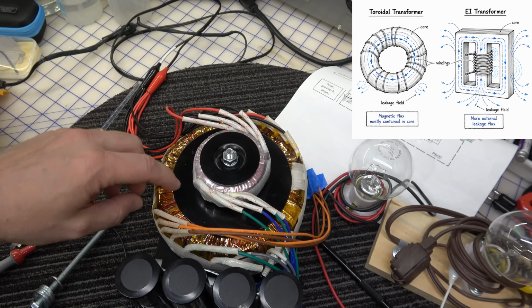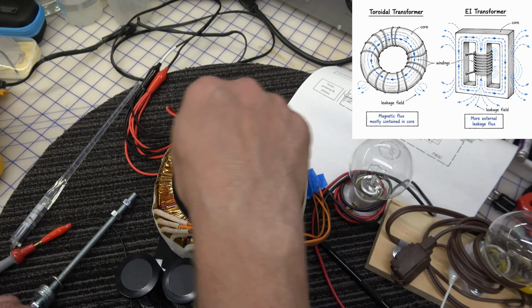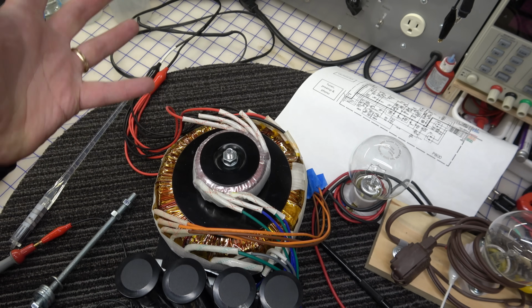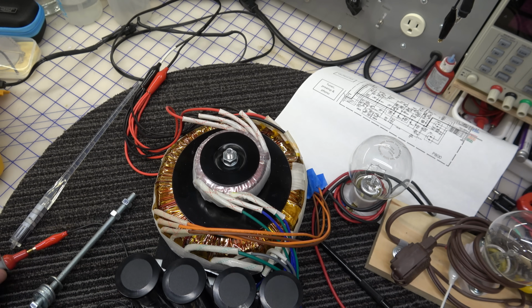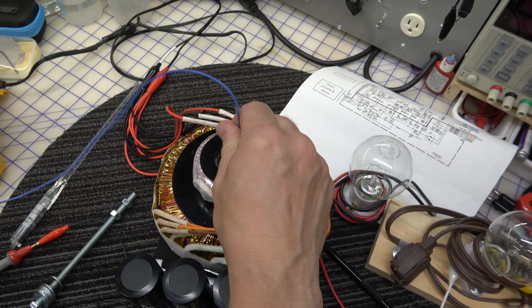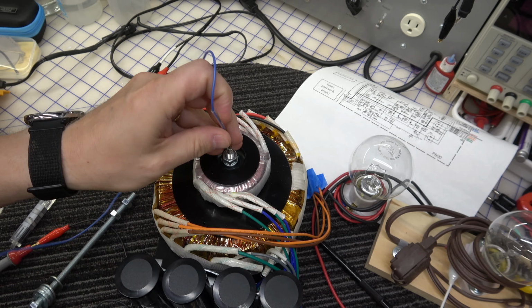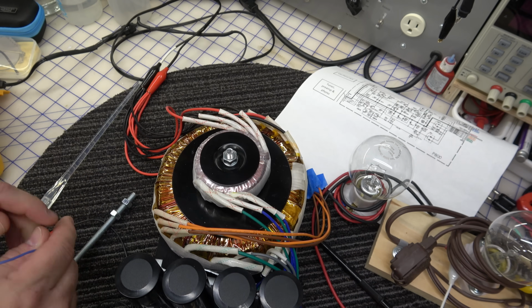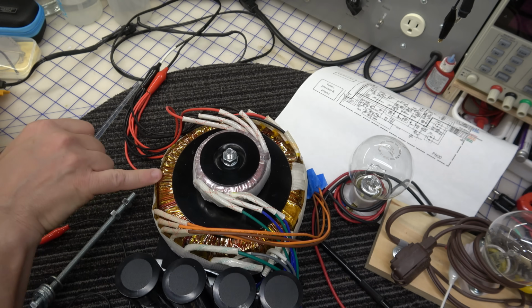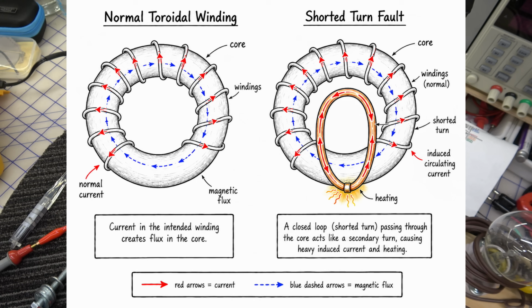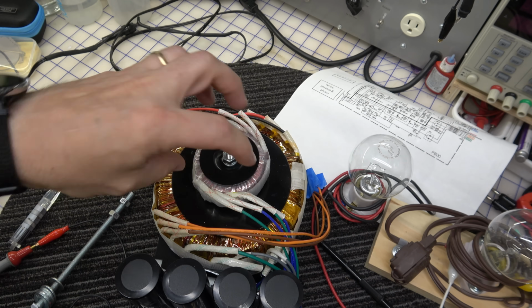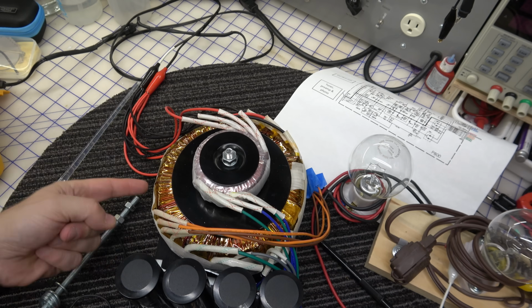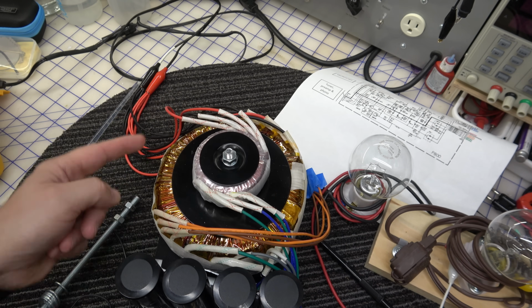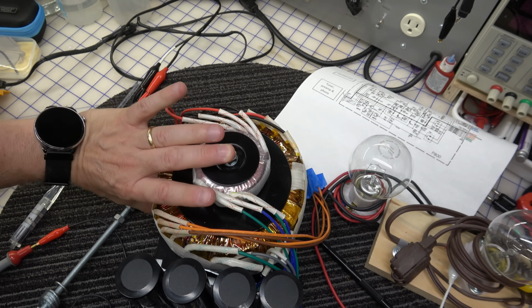So the bottom line is the magnetic field is pretty much neutral inside the middle of the toroid, so putting a metal rod in there isn't going to do anything. What will do it is if I took a jumper - let me show you - and touched this bolt that's going through the middle of the core to ground. What that does is make one complete turn around the coil, just like this, right around the core. That is called a shorted turn, and that will fry the primary of this transformer in pretty short order. So you never want to make a shorted turn. In other words, it's okay for this to be bolted on the top and the bottom, but you do not want it wrapped around. You don't want any metal or any conduction between here and here electrically, because as soon as you do that, you just made a shorted turn.